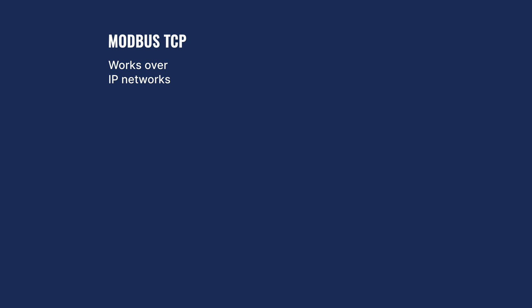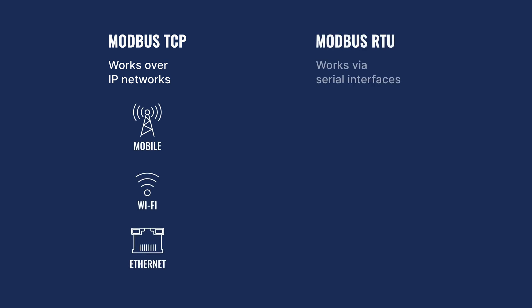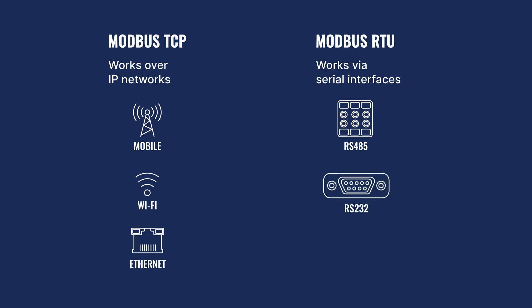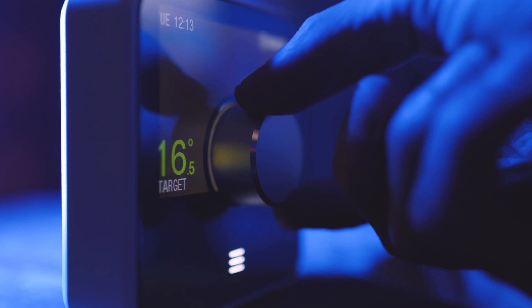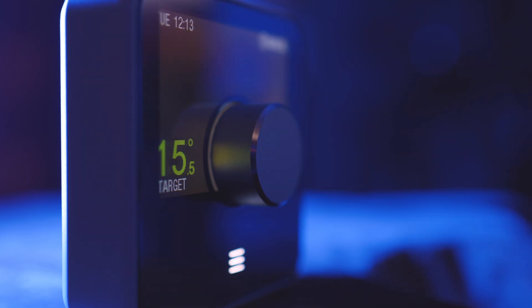Modbus TCP/IP facilitates communication over IP networks, while Modbus RTU enables industrial devices to exchange data using physical serial RTU interfaces such as RS-485 or RS-232. The variation you choose depends on what interface or communication your end device supports. The Modbus protocol is most commonly used in automation systems and is particularly popular in applications where end devices like sensors transmit data readings or control commands to specific targets.